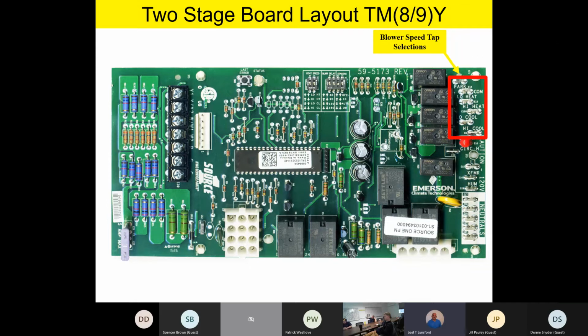Now, when we talk about an ECM motor, we're talking about an electronically commutated motor, which is just a fancy name for a high efficiency motor. But they differ from a capacitor style motor in that they have power to them all the time, and then we provide a 24-volt input to that motor to tell it what to do.